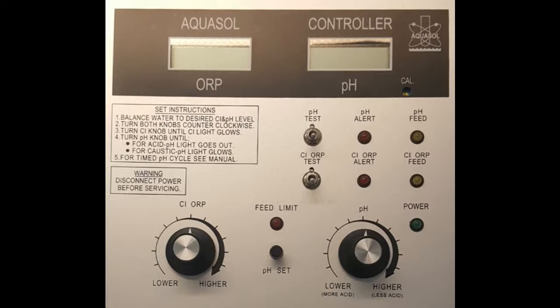And then on the chlorine or CLORP alert, I hate saying chlorine when we're feeding bleach, but obviously it's trying to synthesize a free available chlorine residual. So that alert, you said that it will clear on its own if the ORP comes back into range? Right. Or if you have the number 3 dip switch active, it'll actually go into alert. Now, if you don't want it to continue to feed to get it back up, you just leave number 3 to the left, which is default. Okay. I don't think you guys use that out in the field. That should be staying in the off position. And now, when does that activate? How many millivolts below? Now, doesn't it go into ORP alert if the ORP is too high, if dip switch 3 is off?